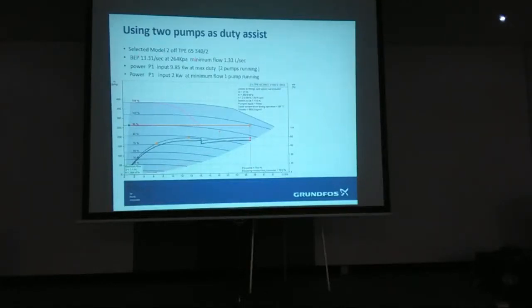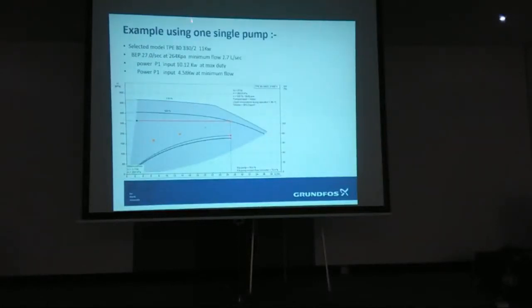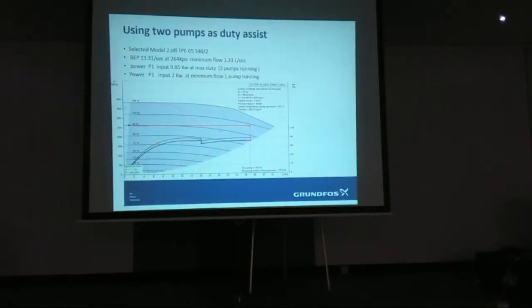Right. So if we use the bigger pump, this is an 11 kilowatt pump, 27 litres a second, 2.7 litres a second minimum flow. Power P1 there is that. Power P1 at the reduced duty, down here, is 4.58 at minimum flow, where it could be the middle of the night, in the sun, whatever, no demand. So if we use the next size up, we've saved energy in this particular example at peak load, and particularly we've saved energy at P1, at the lower duty.